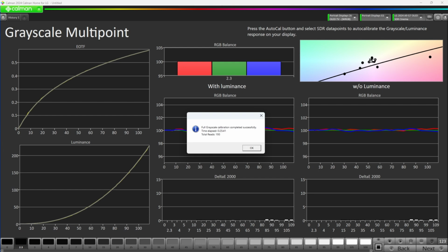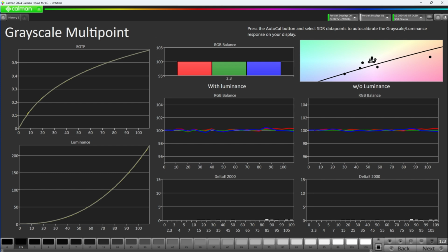Now that that 1D lookup table is complete, go ahead and click OK on the dialog box. And you can see, again, talking about what we saw earlier, that our RGB balance now shows very, very closely aligned balance between the red, green, and the blue. Our DE values are all very, very low. They're almost hard to see on these charts. And then our luminance tracking is tracking right along with our target line. And you can see here that our target line was yellow and the gray is the measured values. Those gray values are now just covering right over the top of that target line.